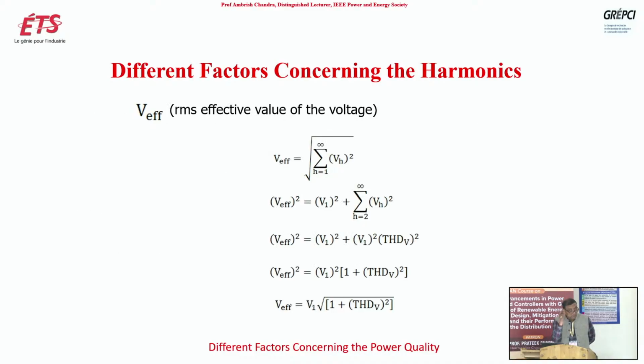Now, the mathematical part of the RMS current we were talking about. We were saying RMS current may have effectively the same losses in the resistance as the DC current. But this is how we calculate the effective RMS current. Starting from harmonic 1, there is some echoing effect.